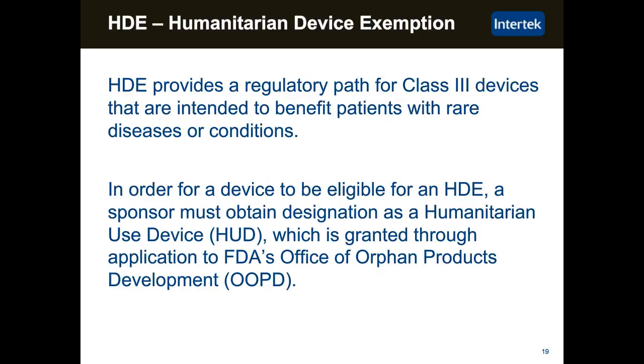The last type that's used less often is a humanitarian device exemption. An HDE provides a regulatory path for Class 3 devices, and in some cases Class 2 devices, that are intended to benefit patients with rare diseases or conditions. In order for a device to be eligible for an HDE, the sponsor must obtain designation as a humanitarian use device through the FDA's Office of Orphan Product Development.